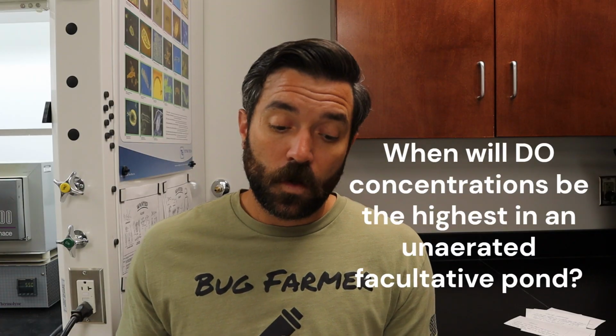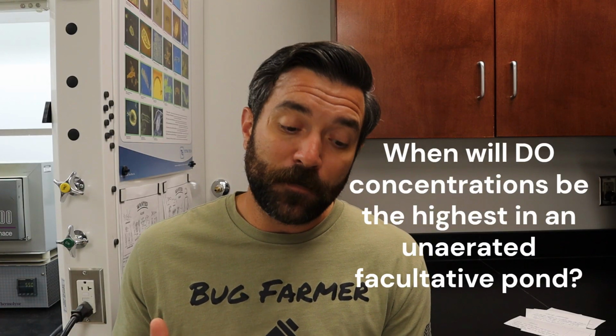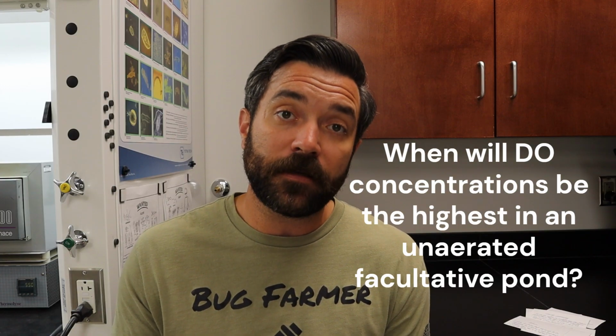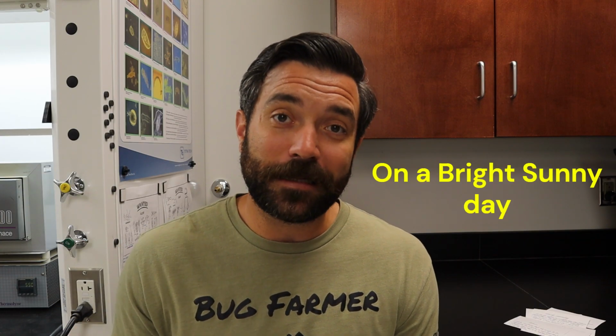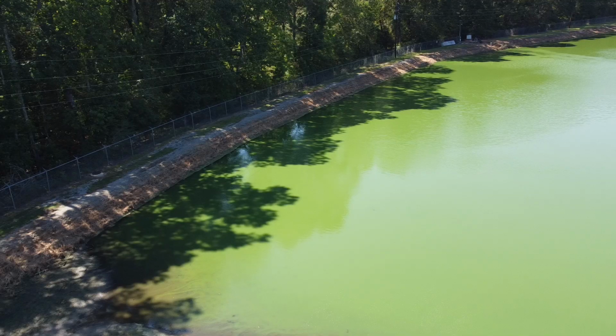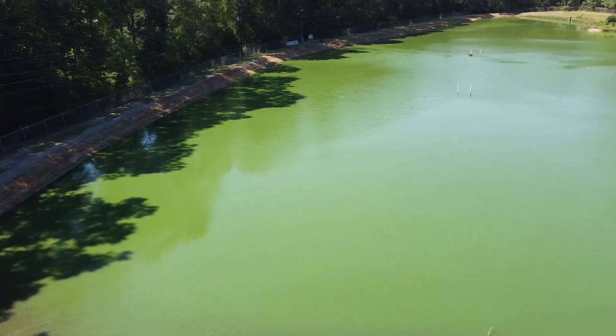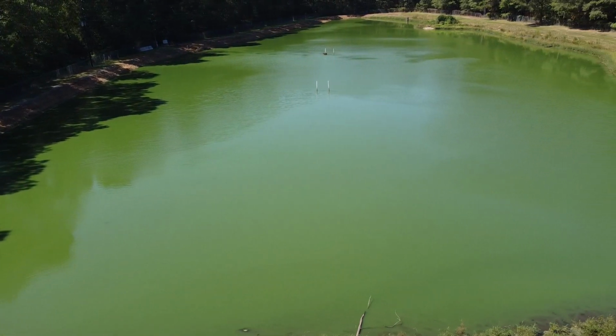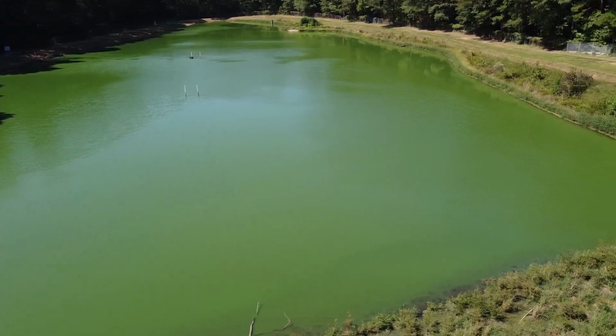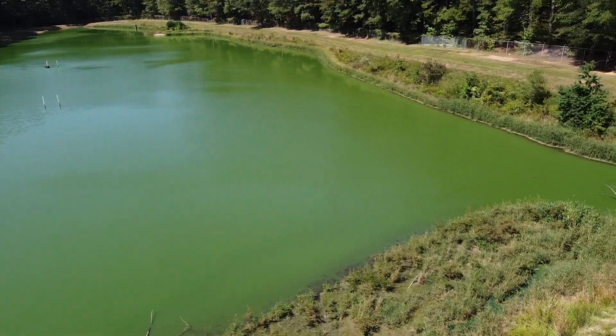Number 7, when will DO concentrations be the highest in an unaerated facultative pond? We should be able to piece this one together after answering those first 6. The DO concentrations will be the highest on a bright, sunny day. Yes, I had to glance at the card because I forgot. A bright sunny day. That means the sun is out, it's over that water, there's lots of photosynthesis happening. That photosynthesis is adding so much DO into the water. So on a bright sunny day, that's when you're going to have the highest amount of DO in your pond.